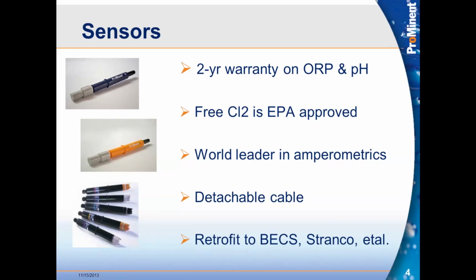Going back to maintenance, all of our probes feature a detachable cable. So those of you that are familiar with an old Strantrol sensor or some of the other chemical controller sensors, that sensor wire is actually molded into the sensor body. And so when you spin out the threads that hold the sensor in place, the coax cable winds up becoming damaged and kinked. The coax hates to be kinked because the shielding, which is critical on that coax cable, becomes compromised, and we wind up getting bad signals from the sensor. So over the years, I've seen just terrible condition on these coax cables that connect the controller to the sensor. So with our detachable cable, that problem goes away.